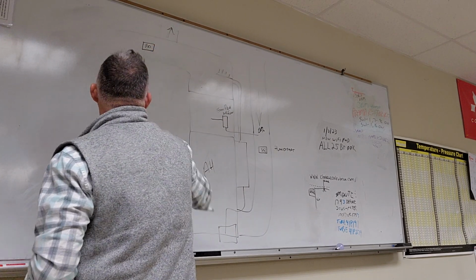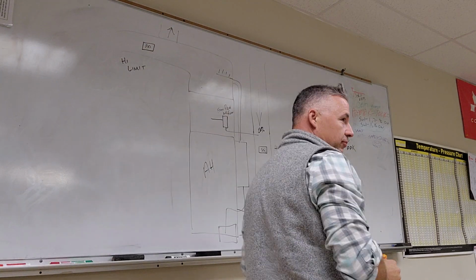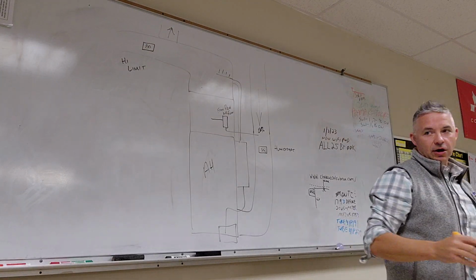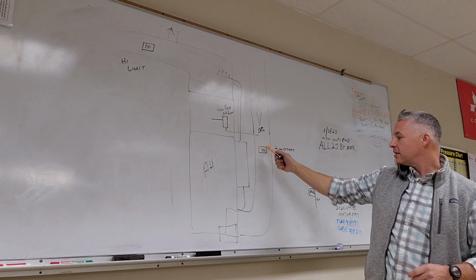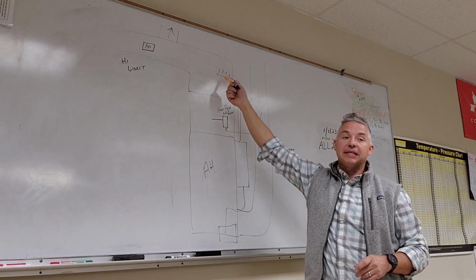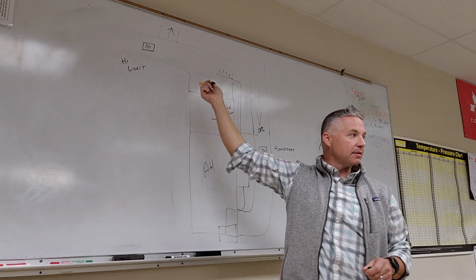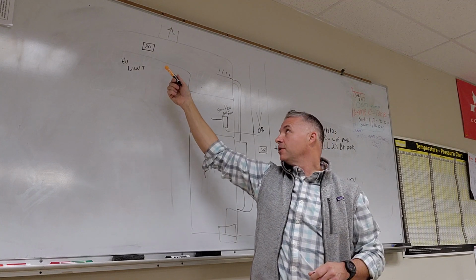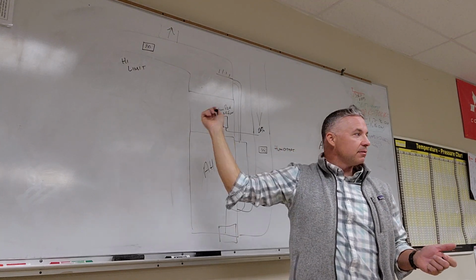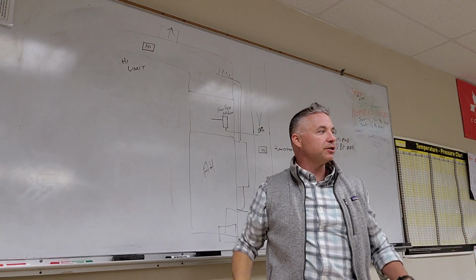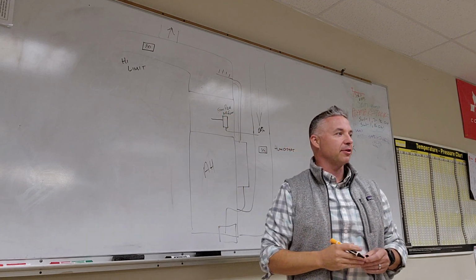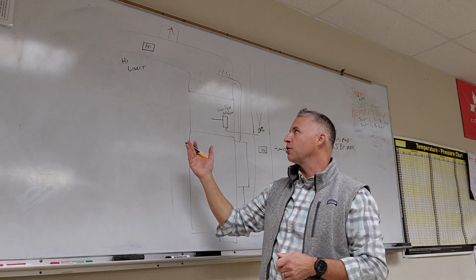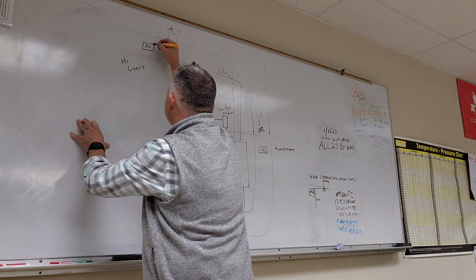We'll call it 80. 50 I wouldn't do, because if we've got 20% coming back and we're dumping steam in at this point, even though it's atomizing in the airstream, you could get a reading of 50%, right? Because you're saturating that air with moisture so that it can get into the house and mix with the air that's already in the house. So 50 is a little bit too low, so we'll call the high limit 80%.